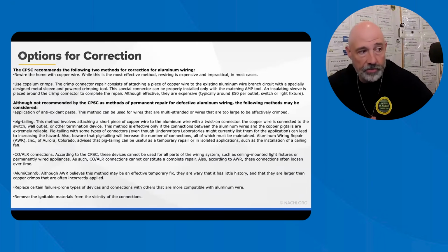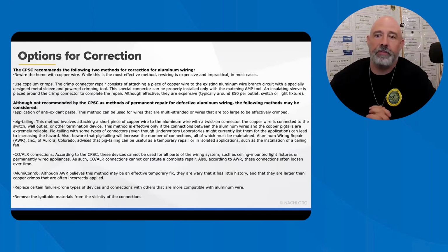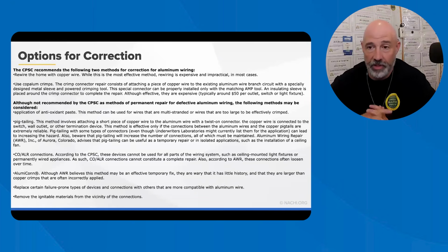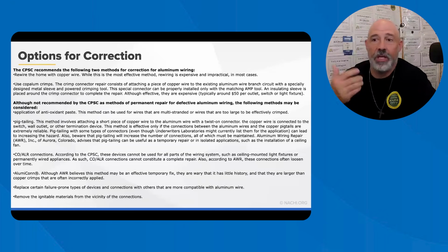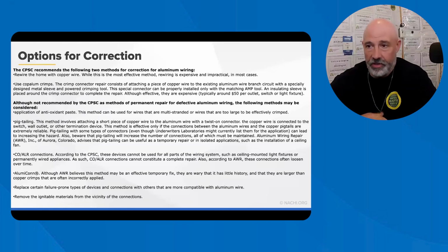Options for the correction of aluminum wiring should be evaluated by a qualified electrician. I've said that a thousand times because they're more experienced in this. They're good at evaluating and checking it. Not all licensed electricians are properly trained to deal with defective aluminum wiring, just FYI. Aluminum wiring can be a fire hazard, so we want to make sure that we call this stuff out if we see it. Again, if you see it.